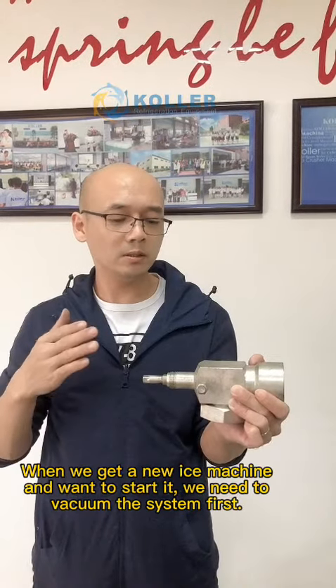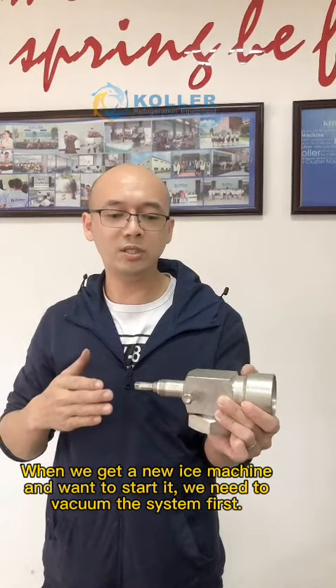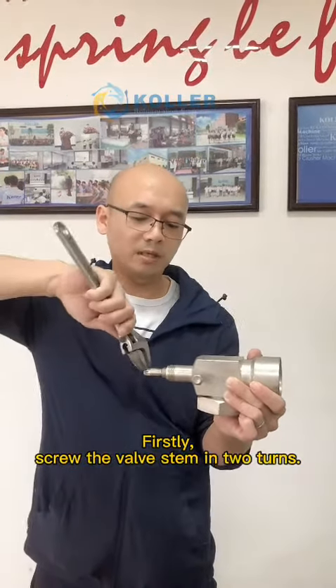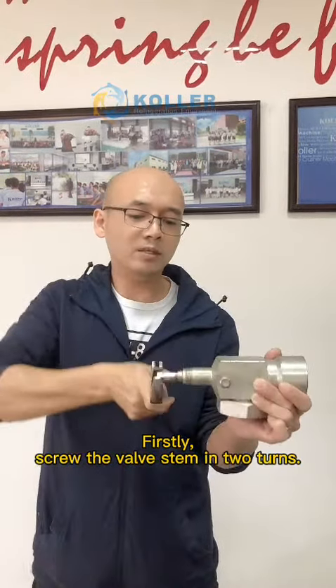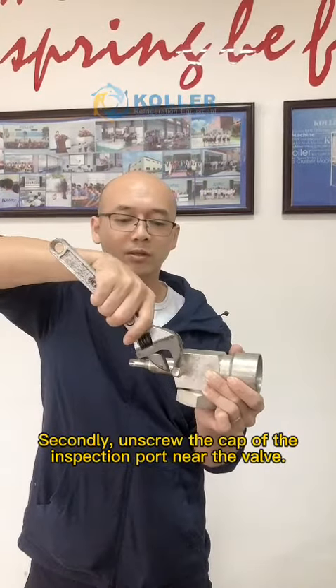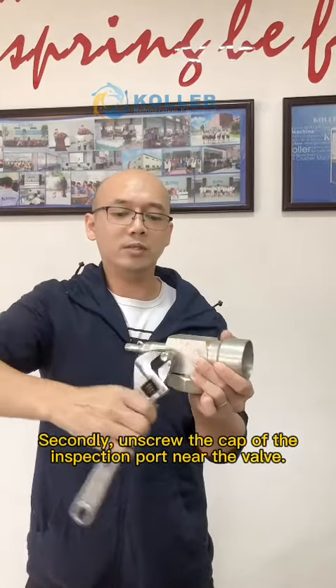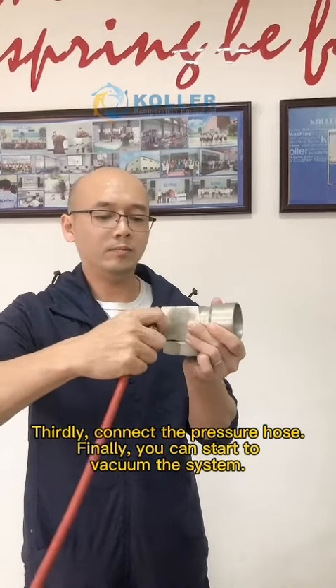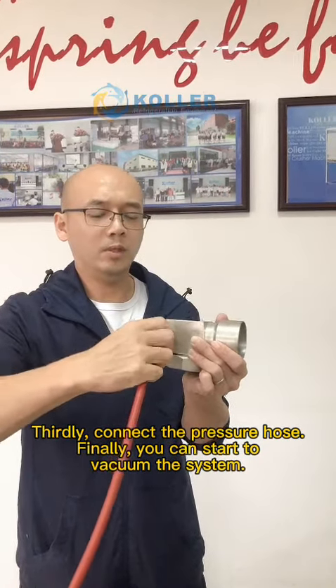When we get a new ice machine and want to start it, we need to vacuum the system first. First, screw the valve stem in two turns. Second, unscrew the cap of the inspection port near the valve. Third, connect the pressure hose. Finally, you can start to vacuum the system.